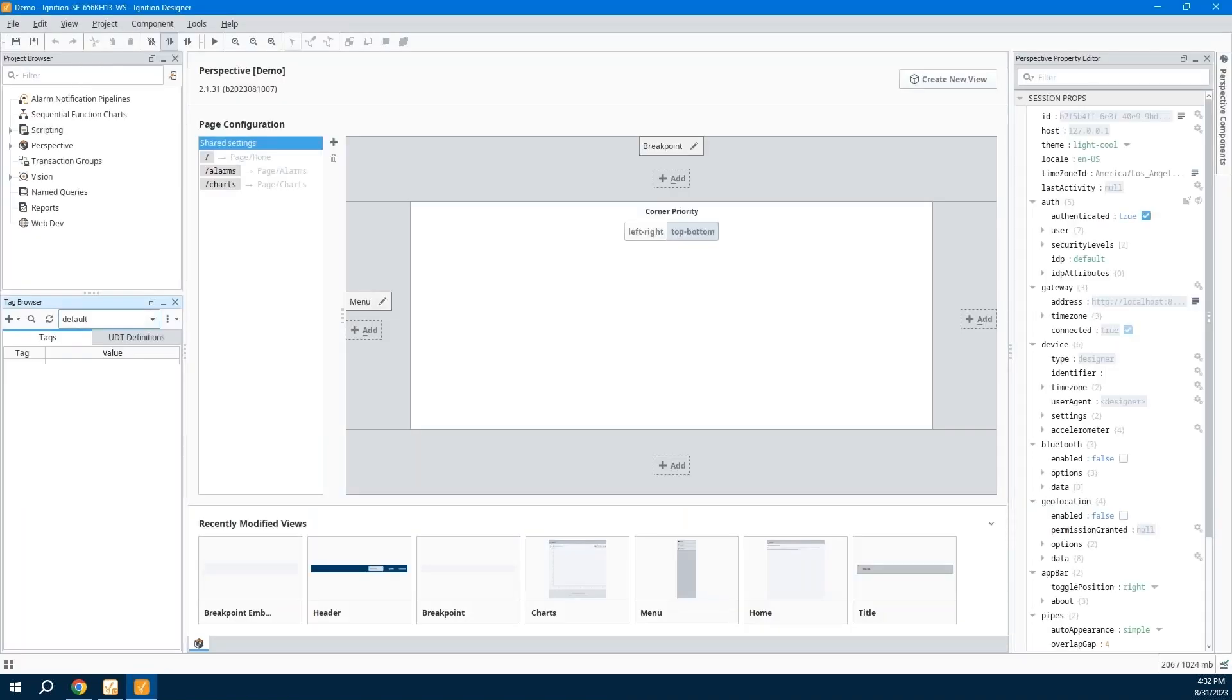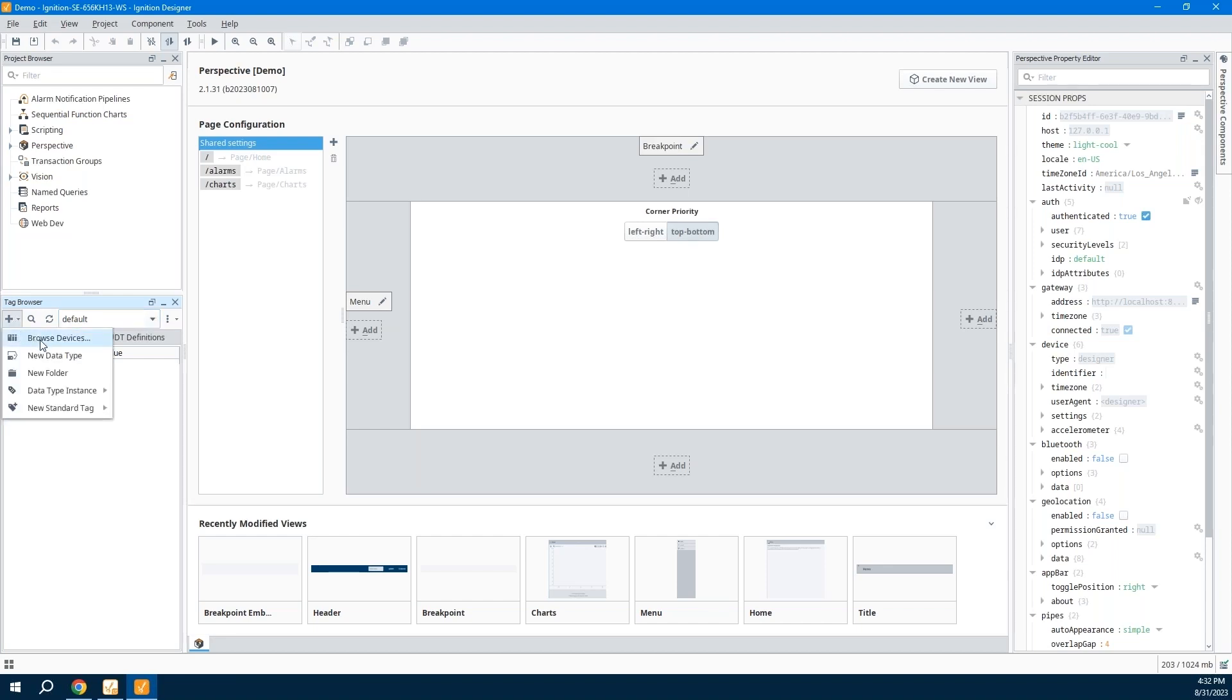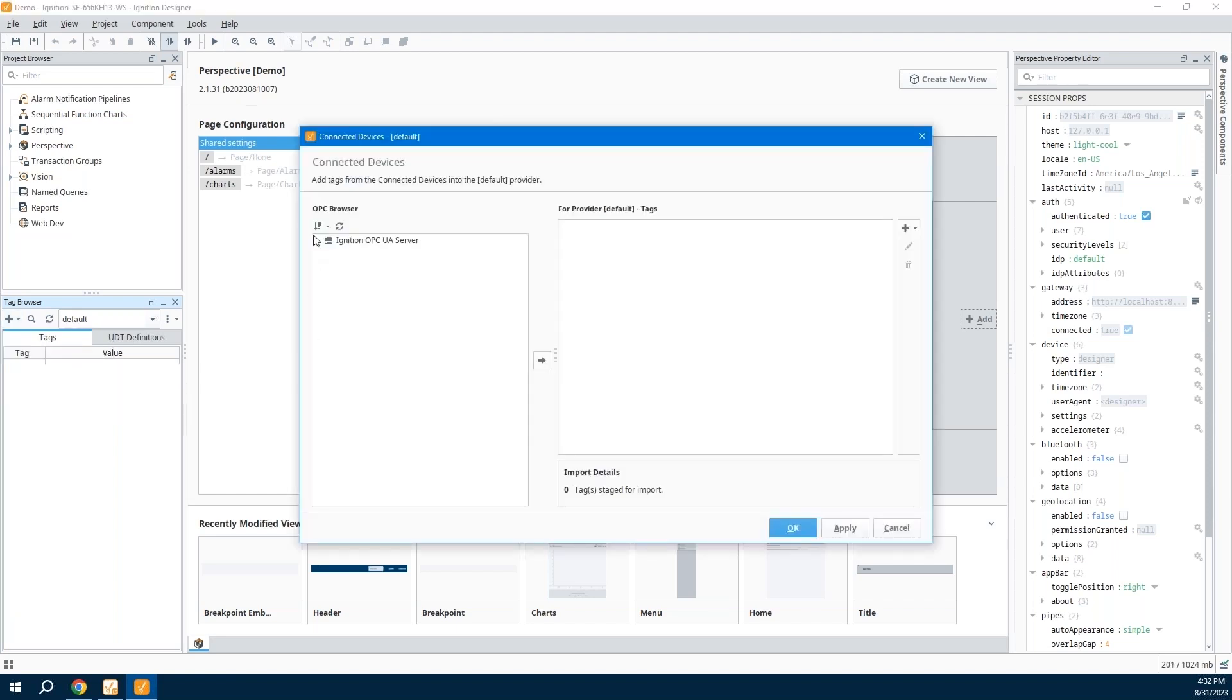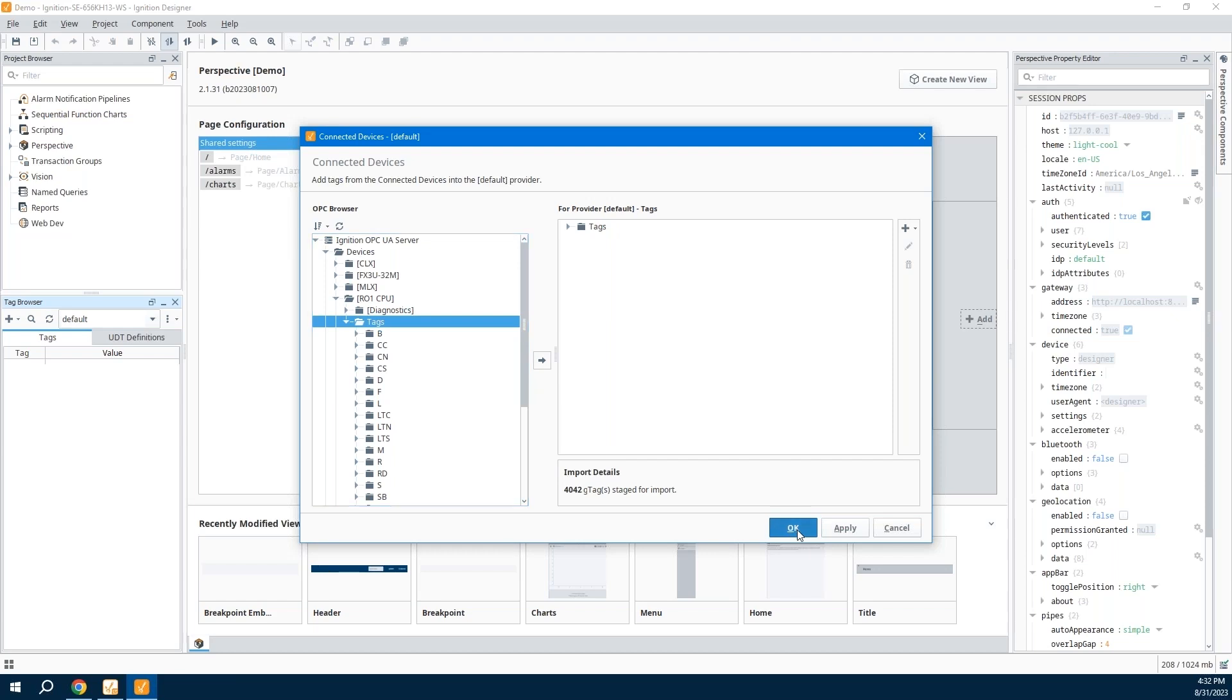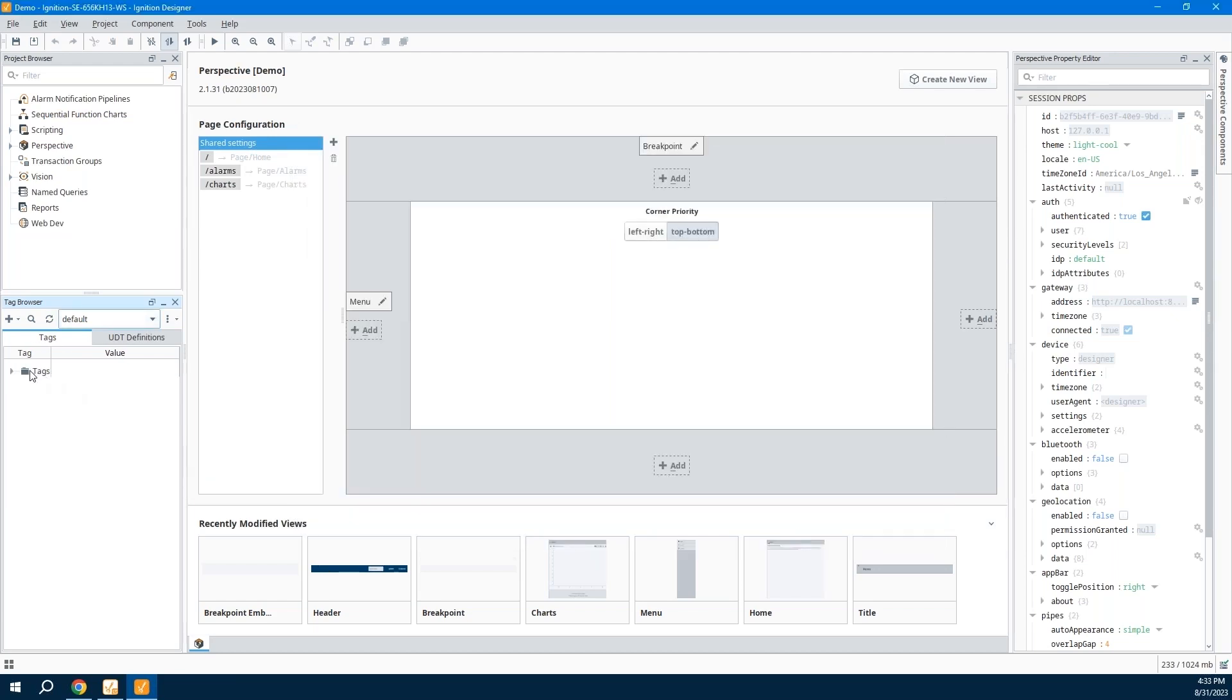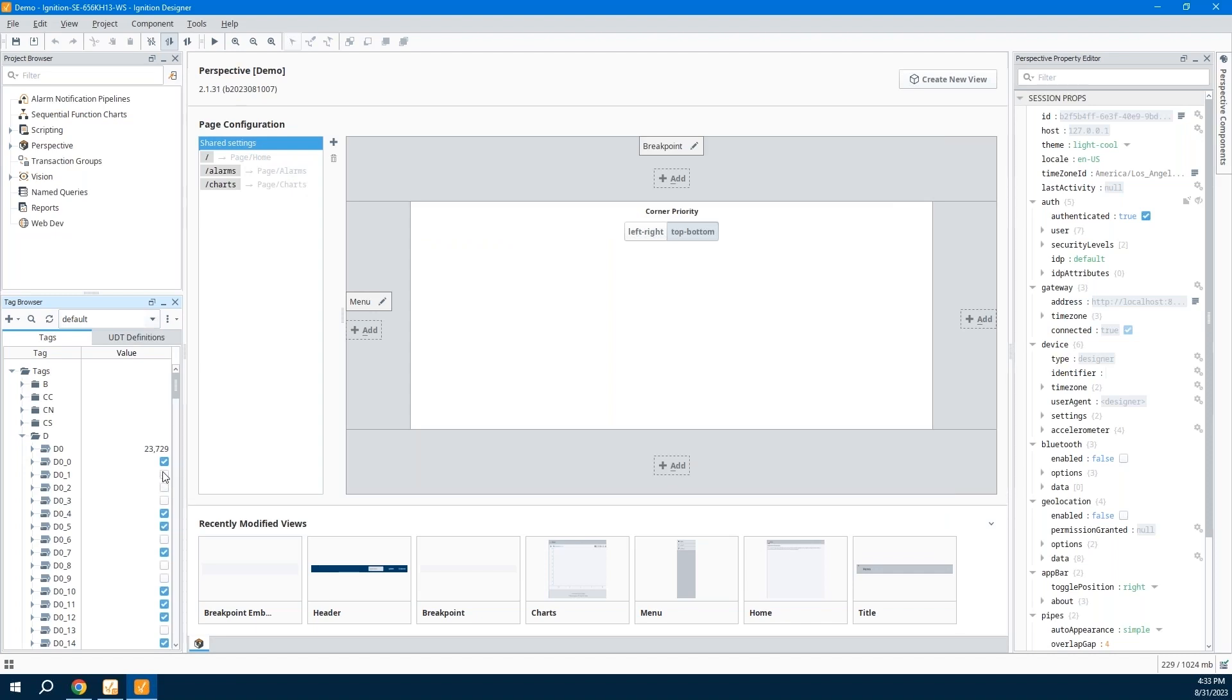We'll create this project. Our design environment here is not limited to just configuring the tag structure, but this is also where you would define the screens that you would build, or to define history or alarms, alarm notification pipelines, all your scripts, all that kind of stuff. So it's one unified design environment. You can see down here, I've got what's called my tag browser, and my tag browser is empty right now because I don't have any tags defined. If I wanted to add tags, I can come and hit this little button up here and I could create individual tags. But what I want to do is browse devices. This is where I can see all those devices that you saw earlier. I can see all those tags we saw earlier and I could pull in individual tags, or in my case, I just want to pull in the entire tags folder. You really have 4042 tags here that you're going to be importing. I now have the tags here, and if I go into these, I can see the real time values coming from that device.